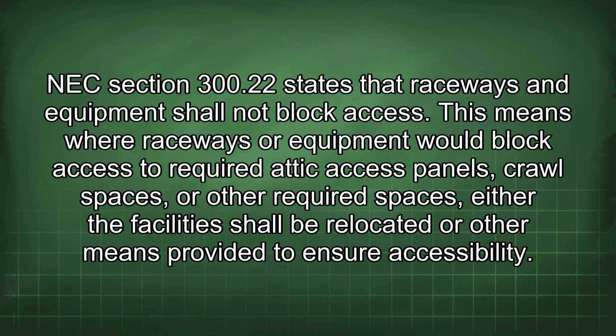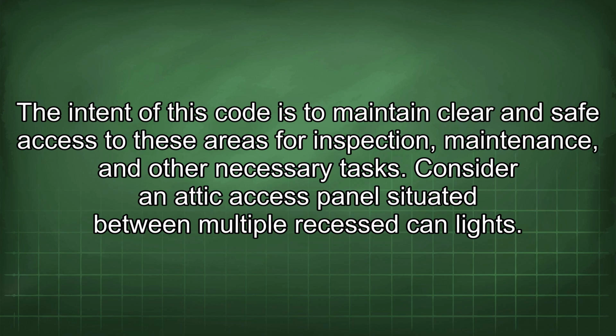NEC Section 300.22 states that raceways and equipment shall not block access. This means where raceways or equipment would block access to required attic access panels, crawl spaces, or other required spaces, either the facility shall be relocated or other means provided to ensure accessibility.